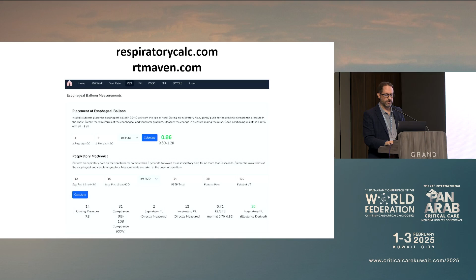At end expiratory pause, I have 12 centimeters of water in the esophagus. An inspiratory pause, 16. My PEEP total is 14, my plateau is 28, the tidal volume is this. And it gives me all the values that I require. There's respiratory system driving pressure, respiratory system compliance, chest wall compliance, directly measured transpulmonary pressure, both expiratory and inspiratory, the elastance ratio, and when multiplied by plateau pressure, it gives me the elastance-derived transpulmonary pressure. So a lot of very useful information from a very simple calculator.